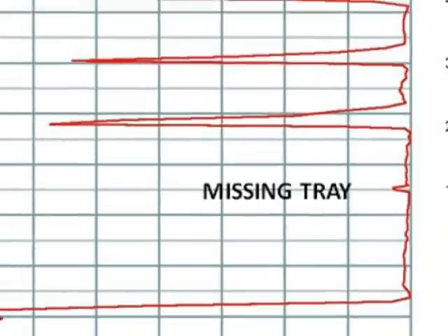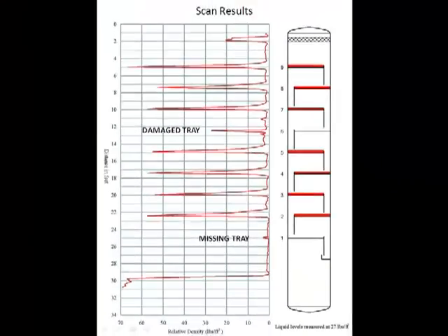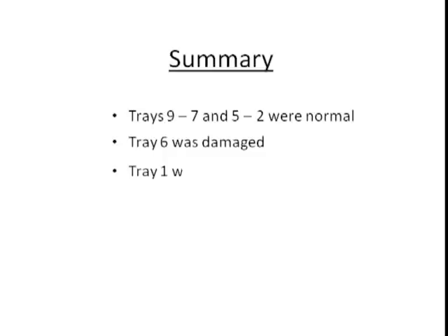And subsequent column entry verified these results. So in summary, the gamma scan showed that trays 9 to 7 and 5 to 2 were normal, tray 6 was damaged, and tray 1 was missing. And with this knowledge, the plant could properly plan for their turnaround, knowing they only needed to replace 2 trays rather than 8 or 9.